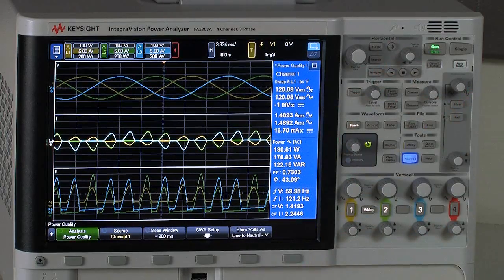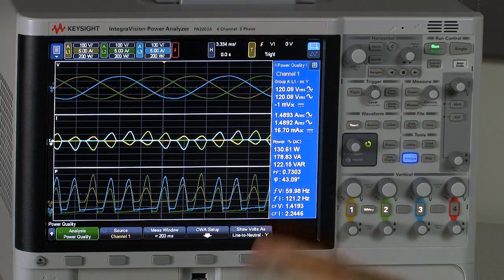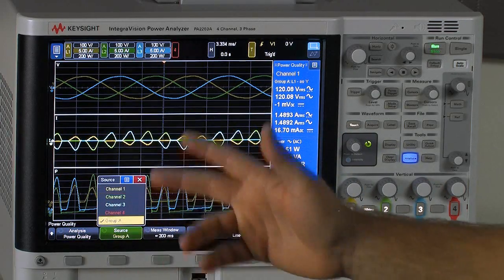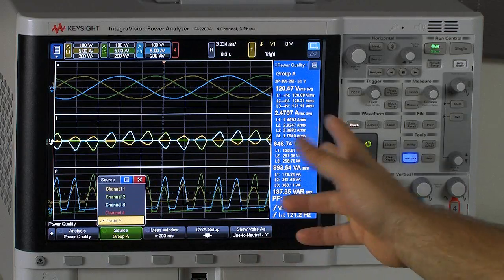So we'll take a quick look here. Now that I've got these group measurements in the power quality analysis mode, I can now, if I go to my source selection here, I can now choose group A, which is again channels one, two, and three.